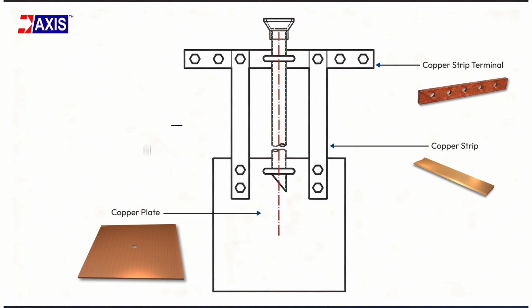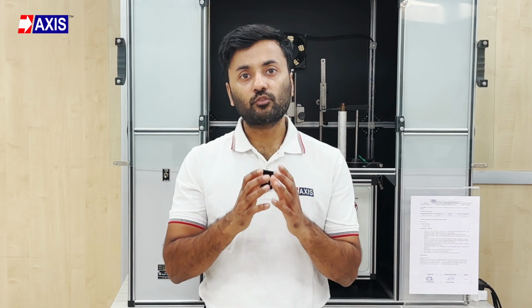Now fourthly, the GI pipe. This GI pipe is a perforated pipe for watering as shown in the diagram. Its job is to carry water down to the soil around the copper plate so the moisture level stays stable. Moist soil keeps the resistance low and helps the fault current move into the ground quickly, and the holes along the pipe allow the water to spread around the plate. This pipe is made of galvanized iron so it can stay in the soil for long periods of time without corroding.